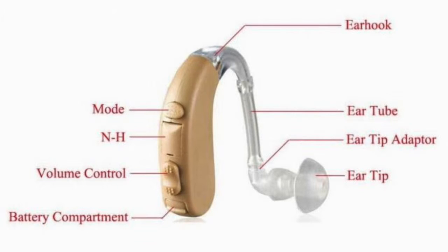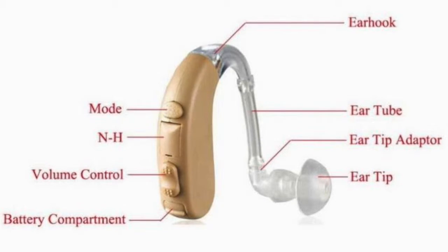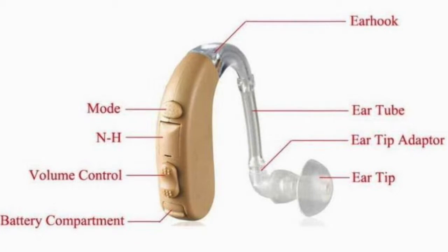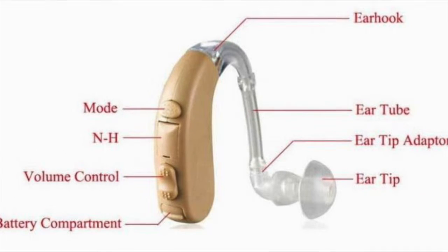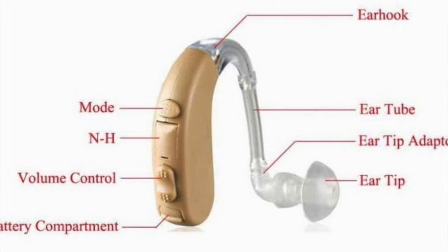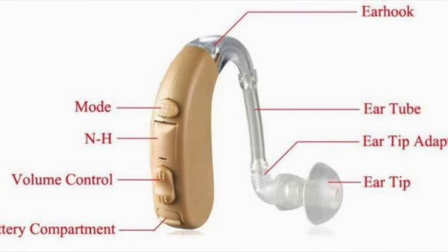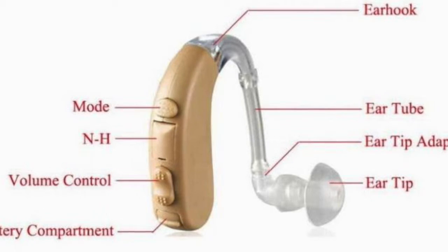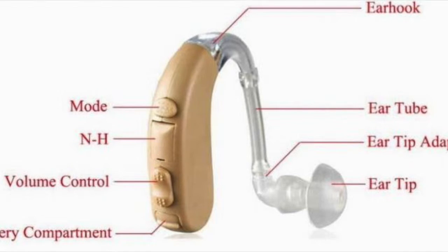Hearing aids have different parts. For example, a directional microphone, which is a part of a hearing aid that determines where important sound comes from. Then comes a microphone, which picks up sounds and sends them into the amplifier. Then the connecting tube that fits into the ear hooks transmits the electronic sound from the mic. And the ear mold, plastic or acrylic components, fits snugly inside your ear canal and concha bowl. It provides an acoustic seal for the electric sound.